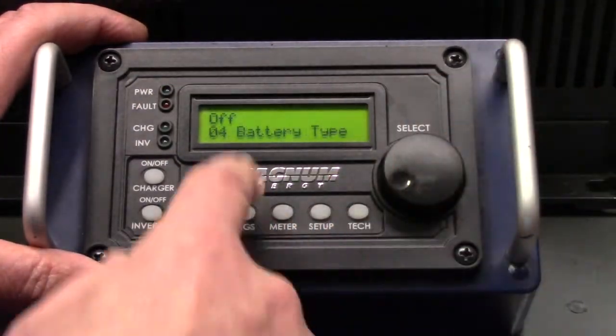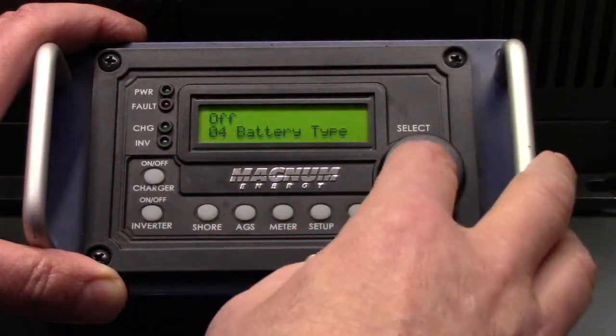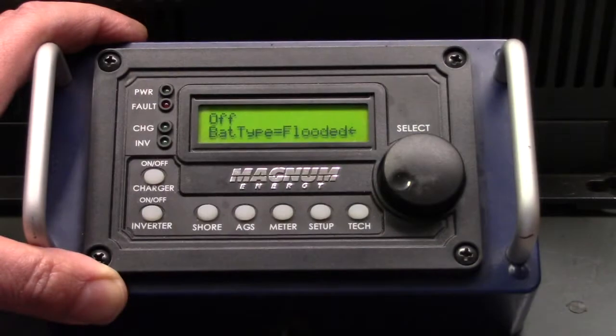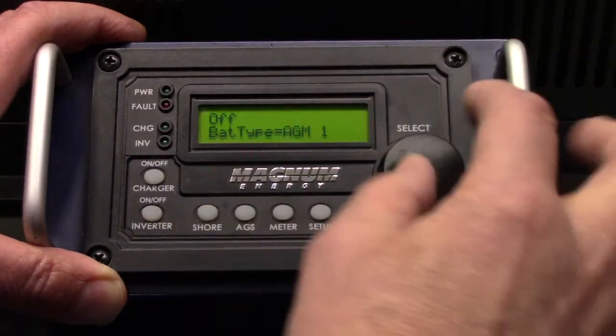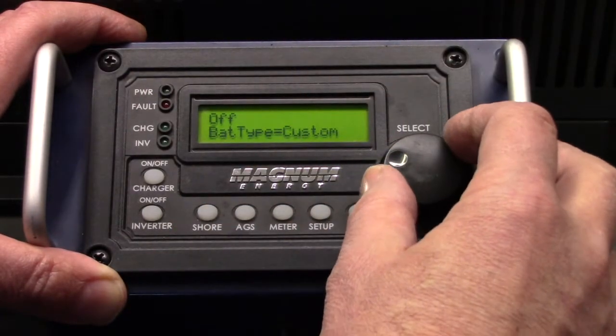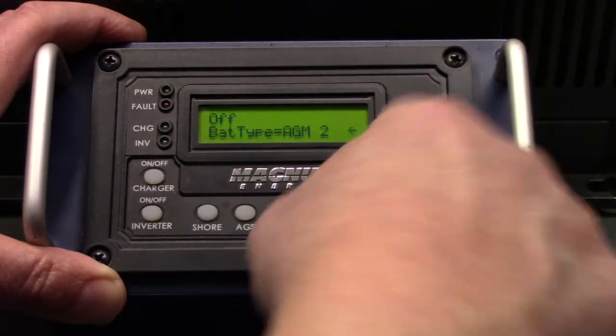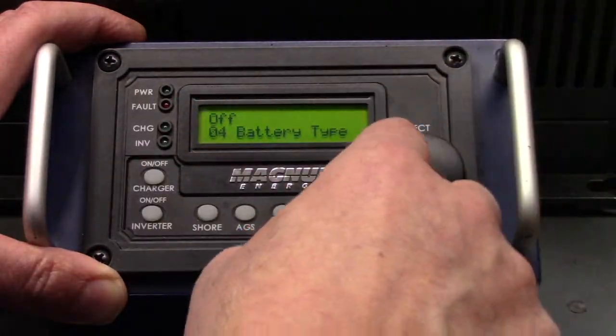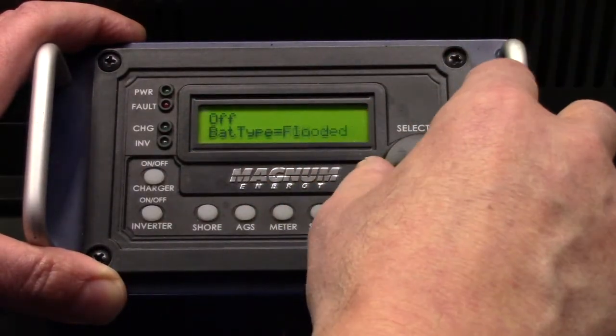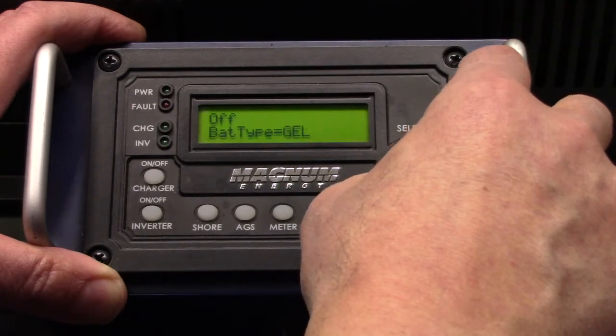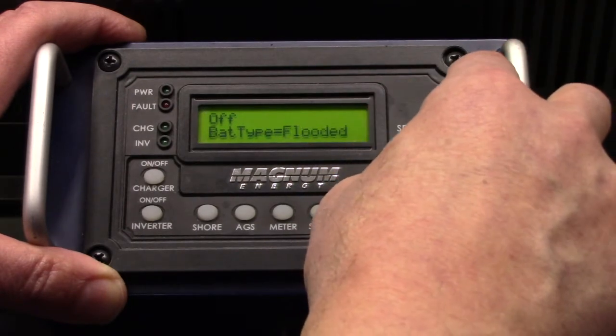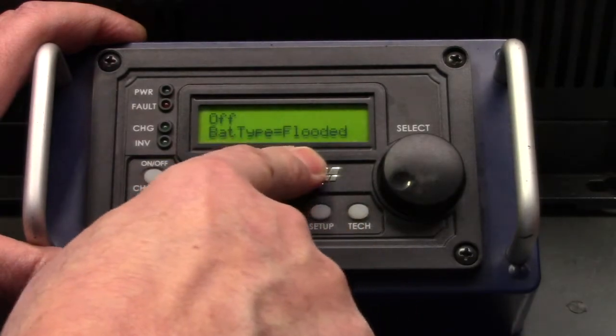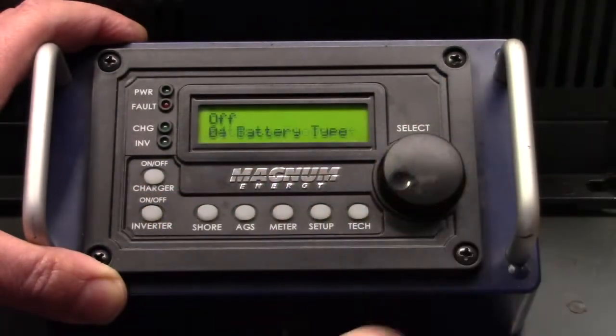Next one is battery type. You definitely have to make sure this is set correctly. Flooded is your typical lead acid battery. You also have other settings like AGM and gel types, for different types of batteries. If you wanted to change it, push it and see the arrow change. Back in, let's go back down to flooded. So for your typical lead acid battery, you want to set it to flooded.